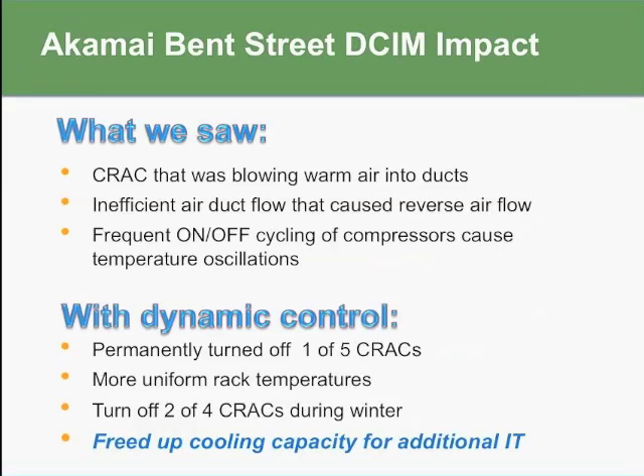So some other things that we saw: one of the CRAC units was blowing warm air into the ducts, as I mentioned, but we also found inefficient air duct flow that caused reverse airflow in some cases, which again led to inefficient cooling. And we also noticed frequent on-off cycling of the compressors of the CRAC units caused temperature oscillations, which again is not what the equipment wants to see. It wants to see consistent temperatures, not oscillations in temperature.